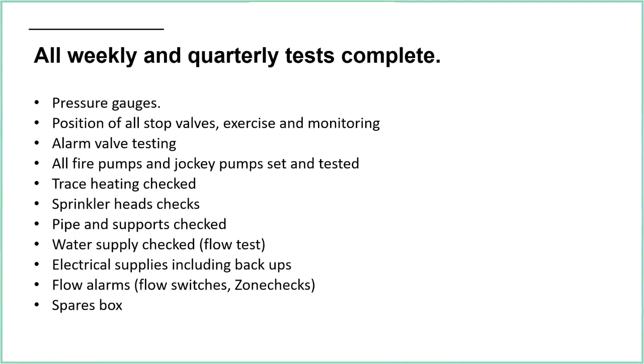So again, that's setting all the pressure switches, making sure that the pump comes in at the appropriate pressure, the jockey pump coming in and out, so the cut in and cut out pressure of the jockey pump, and all testing related to that. Trace heating checked, sprinkler heads checked. So as far as commissioning and handover is concerned, remember all of those little clips need to be removed. And obviously heads and supports checked to drawing, are they in the correct position?